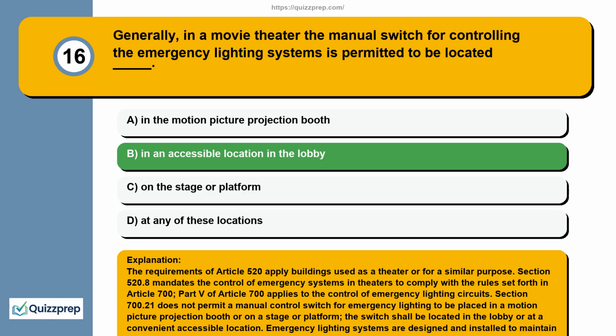The requirements of Article 520 apply to buildings used as a theater or for a similar purpose. Section 520.8 mandates the control of emergency systems in theaters to comply with the rules set forth in Article 700. Part 5 of Article 700 applies to the control of emergency lighting circuits. Section 700.21 does not permit a manual control switch for emergency lighting to be placed in a motion picture projection booth or on a stage or platform. The switch shall be located in the lobby or at a convenient accessible location. Emergency lighting systems are designed and installed to maintain a specific degree of illumination for means of egress of the building in the event of fire or a similar emergency, or if the normal power supply fails.